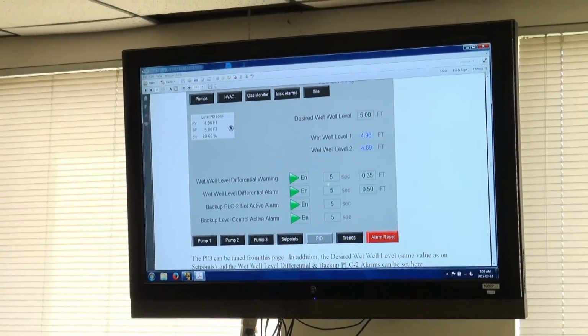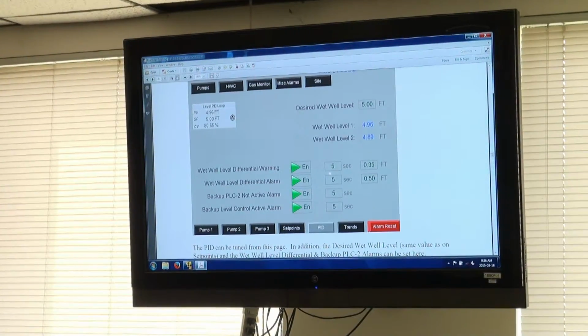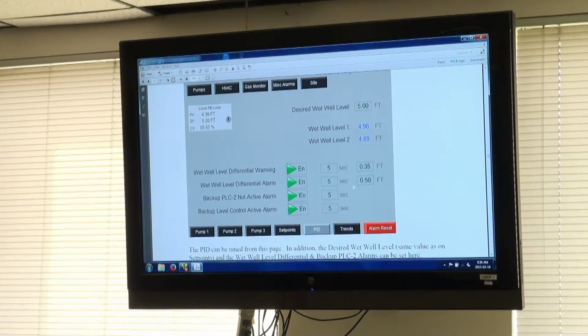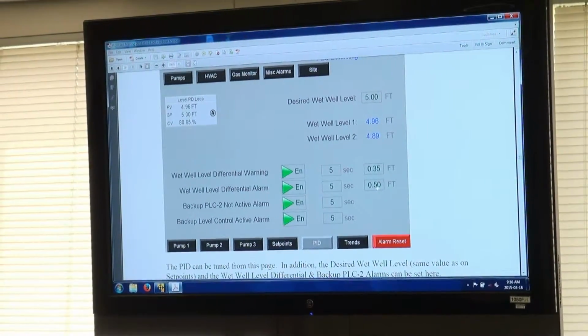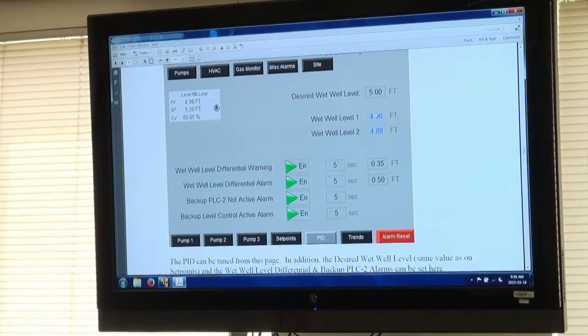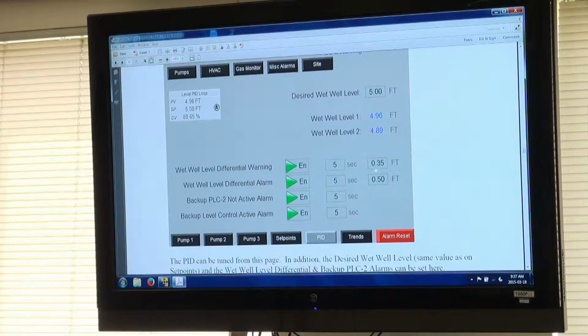These alarms, we could increase them if they become a nuisance. If you're constantly seeing these at SCADA, we could either increase the delay or we could increase the difference of the level. But what that looks at is if in this case one level is 4.96, the other is 4.89. The difference between them is 0.07, so neither of these alarms would be triggered. If this was 5.96, then we'd be a whole foot away, and then both these alarms would be triggered. What that's really trying to do is tell you there's probably something wrong with one of the levels, and that's the purpose of that. But again, if you're getting too many of them, we can change the level difference or the delay.